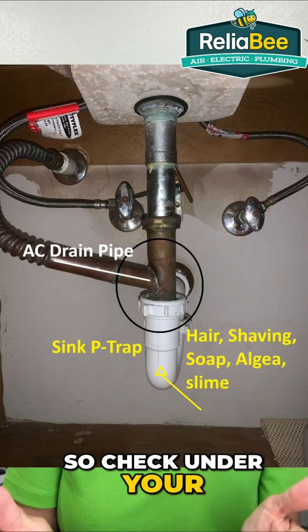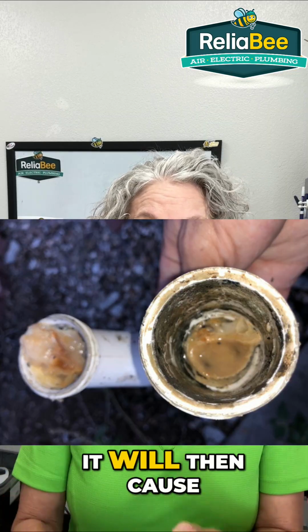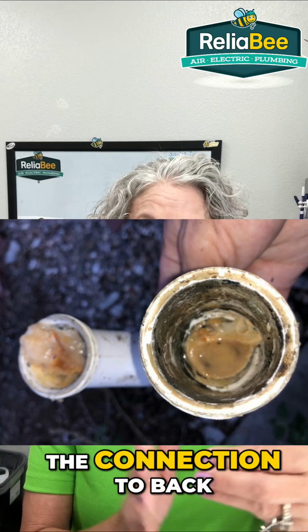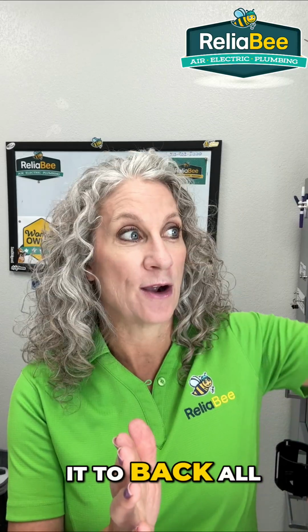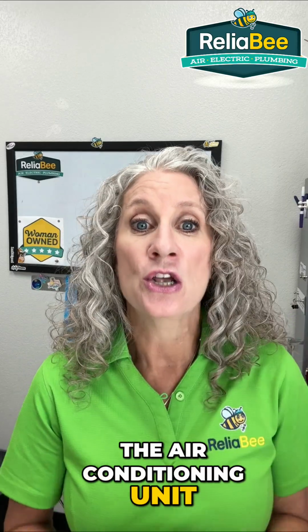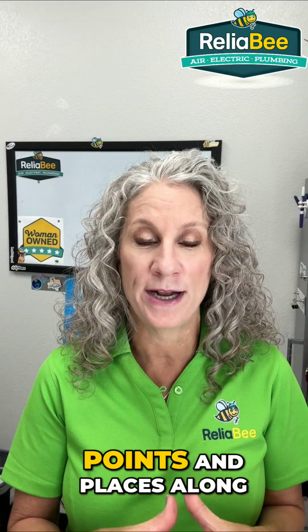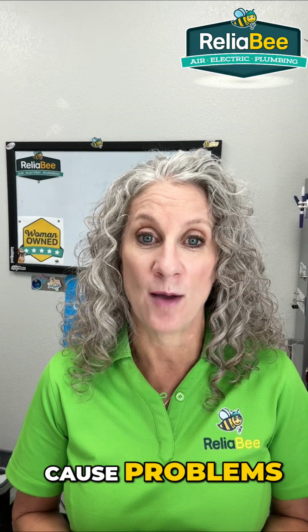So check under your bathroom sinks. If the sink itself is clogged, it will then cause the connection to back up and then cause it to back all the way up to the air conditioning unit. So there are several points and places along the line of an AC drain that can cause problems.